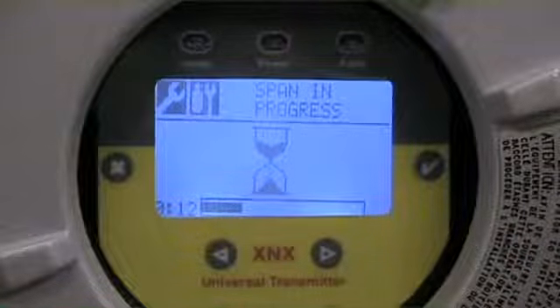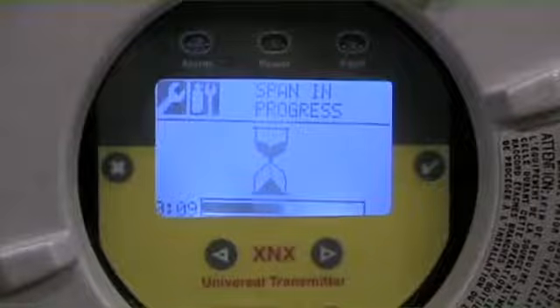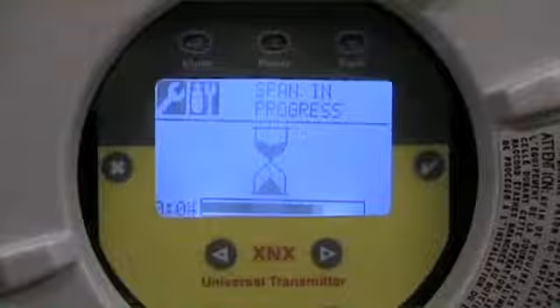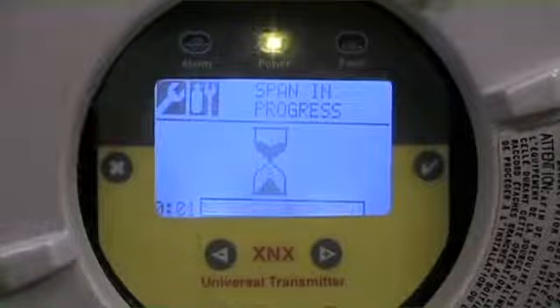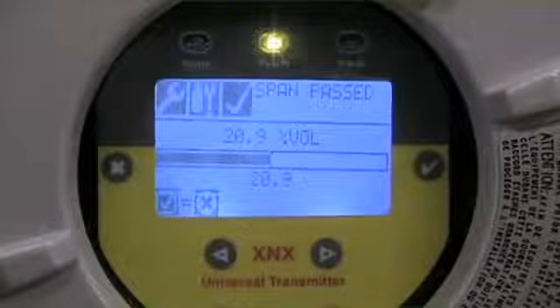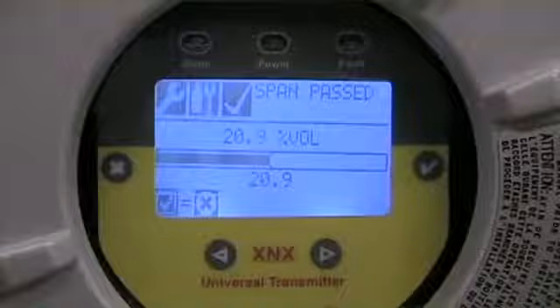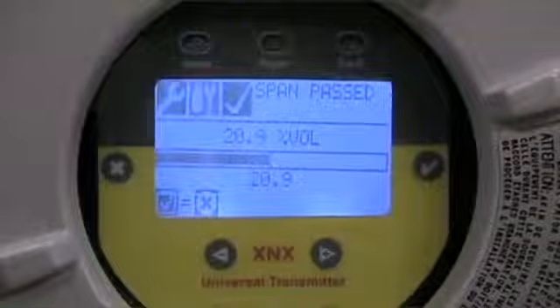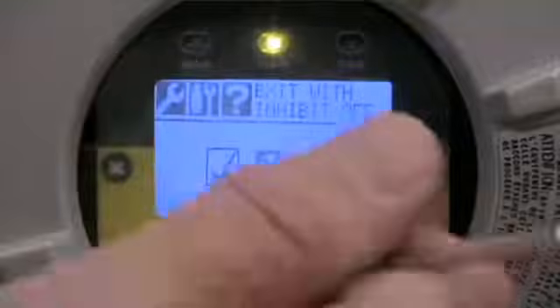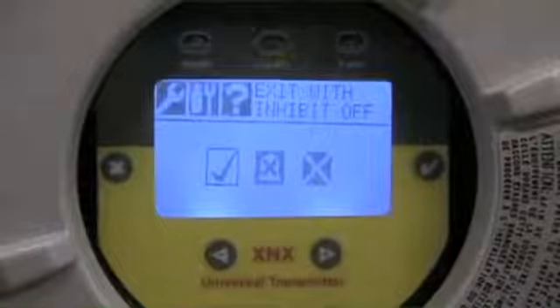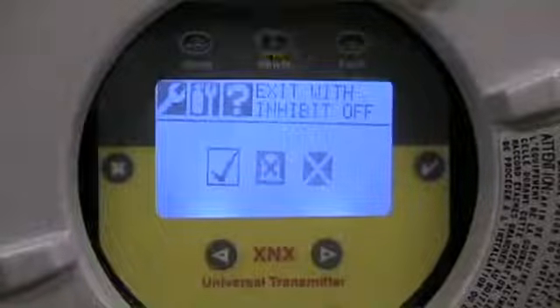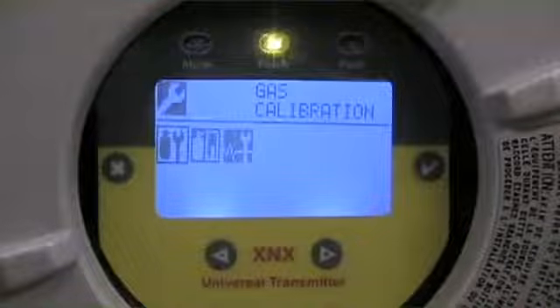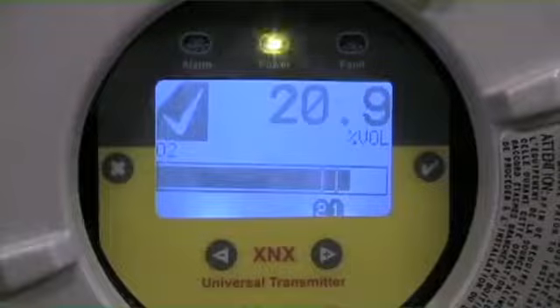And the instrument is now spanning. So you've allowed gas to stabilize and flow, and now the instrument's saying, this is what my challenge concentration is going to be, or it's what's going to be reported. So in this case, the process is actually changing the output to make sure it's in range. In this case, the instrument's accepted, it passed. If there was a condition where the sensor was aged, wasn't able to be calibrated anymore, this is where you'd get an indication telling you that you've faulted out, you don't have enough range left in the sensor. So we've passed, that's acceptable, and again, now we can come back with this screen turning off the inhibit, which we talked about in a previous video, where we're sending off an inhibited signal to not set off alarm functions, and then we accept that function and we're back into our main menu for calibration. We can exit out of this completely, and we're back into a standard reading with now a newly calibrated sensor.